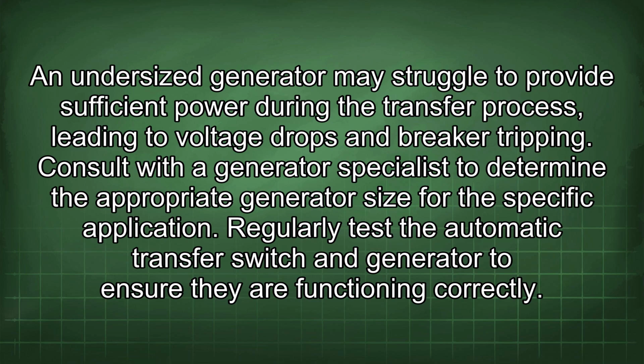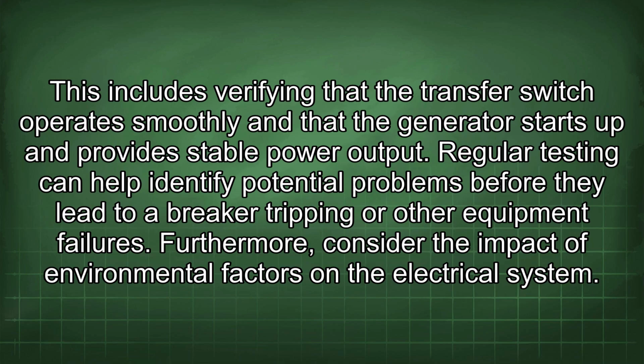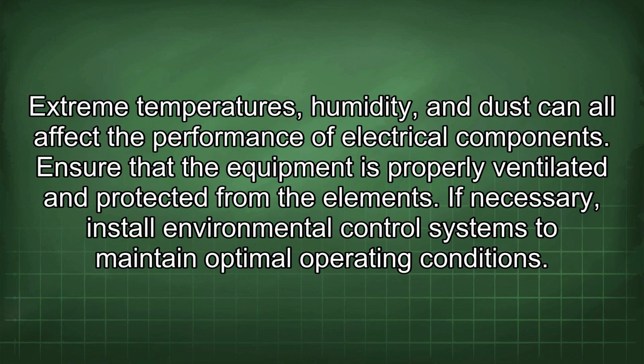Regularly test the automatic transfer switch and generator to ensure they are functioning correctly. This includes verifying that the transfer switch operates smoothly and that the generator starts up and provides stable power output. Regular testing can help identify potential problems before they lead to breaker tripping or other equipment failures. Furthermore, consider the impact of environmental factors on the electrical system. Extreme temperatures, humidity, and dust can all affect the performance of electrical components. Ensure that the equipment is properly ventilated and protected from the elements. If necessary, install environmental control systems to maintain optimal operating conditions.